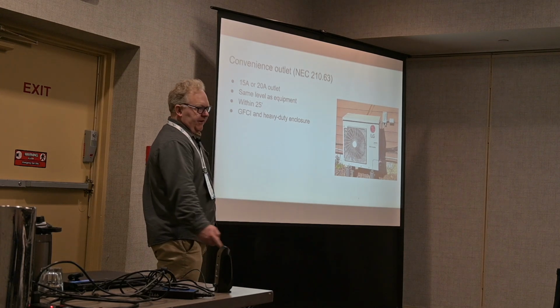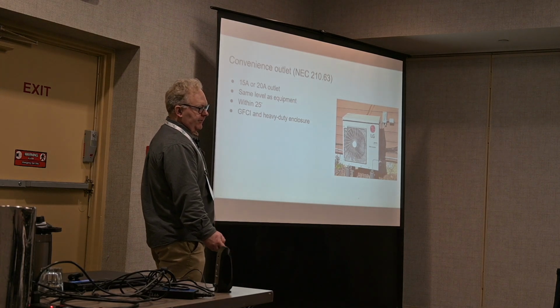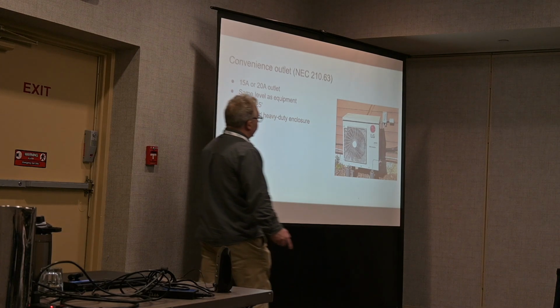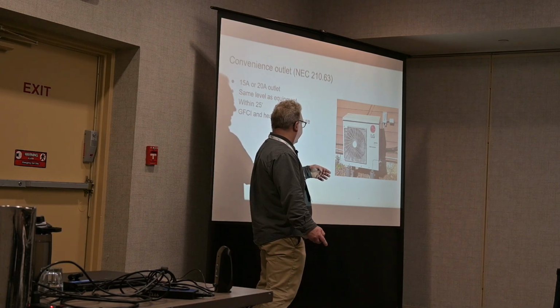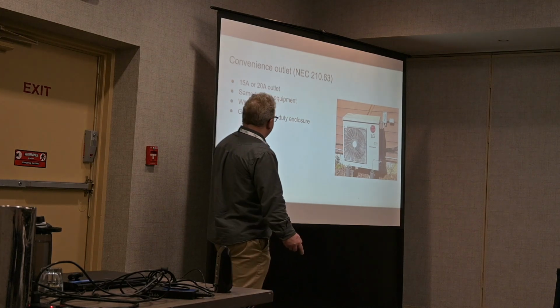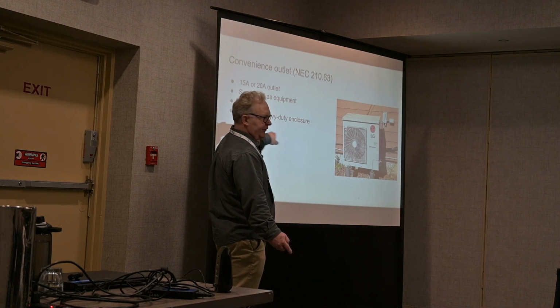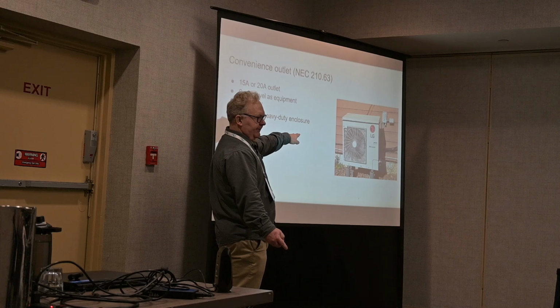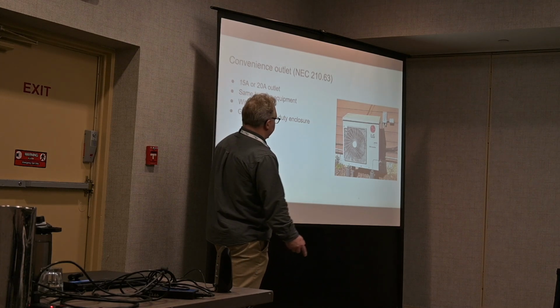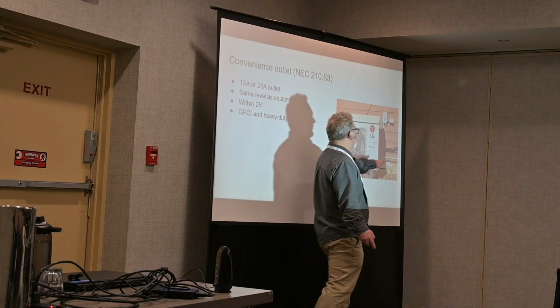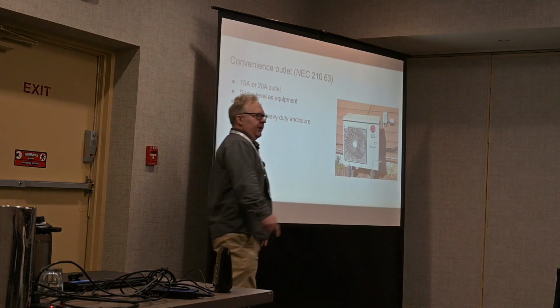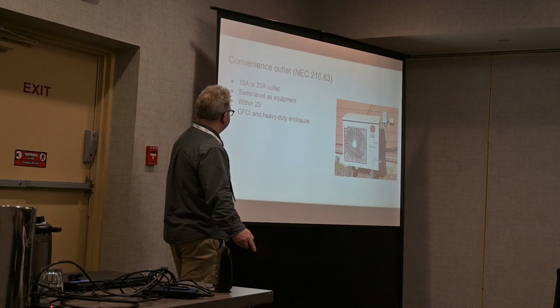There needs to be a convenience outlet within 25 feet. This is for the technician working on the heat pump to plug in their tools. If there's already an existing GFCI outlet within 25 feet, you're good to go. If not, you're going to need to install one, and it's going to need to be on its own breaker. It can't pull power from the 240 volt circuit.